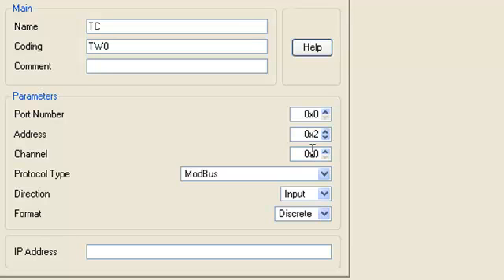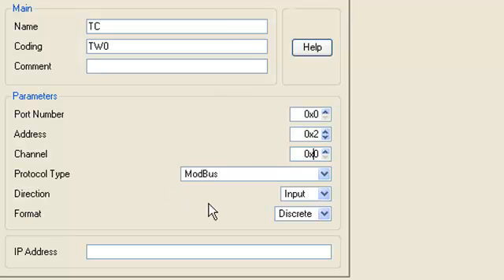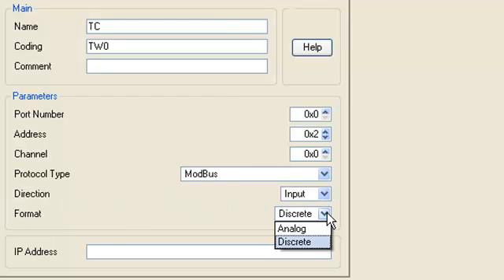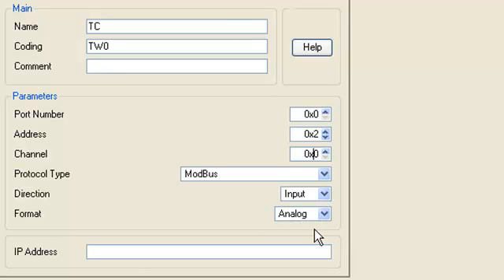Since the module's address in network is 2, so the setting address should be equal to 2. The starting address of the input register must be set to 0 because number 3 is the data type identifier and the Modbus starting address entries mode is 0. The setting protocol type ModBus, direction input, format analog.